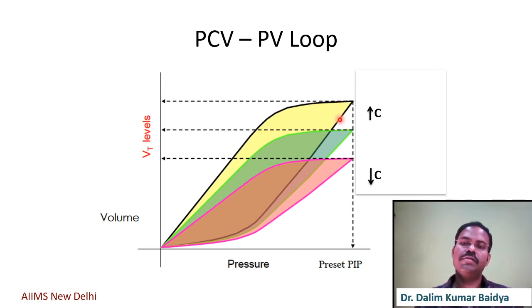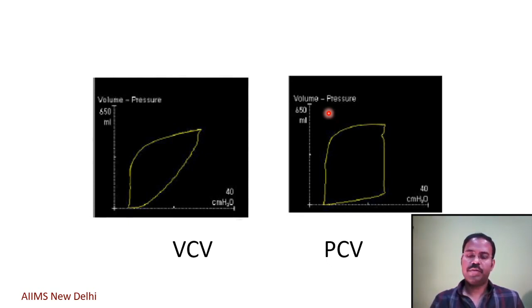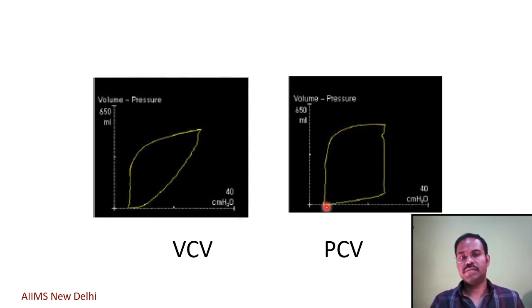If you observe closely, there is a subtle difference in the PV loop characteristics of VCV mode versus the PCV mode. As you are aware, in the PCV mode, the pressure rises fast in the beginning of inspiration and reaches the peak inspiratory pressure. Then throughout the inspiration, it is maintained at that level. So if you look at the PV loop for the PCV mode on the right hand side picture of your screen, this will look the same. Initial rise in the pressure and then the pressure is maintained constantly. This will give the PV loop an appearance of a square wave in comparison to the elliptical nature of the PV loop in VCV mode.